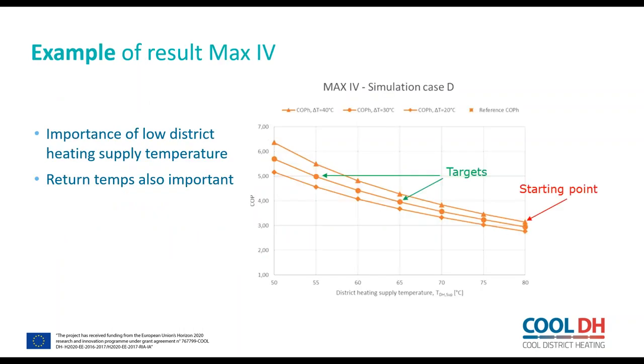An example of the results from the Max 4 looks like this, where we vary the temperature on the hot side, and we also vary the temperature on the cold side. So what you can see in the graph is that at the starting point where we have 80 degrees supply temperature and we have a temperature difference of 40 degrees, you get a COP of about 3. Then with a reduced supply temperature going left in the graph, you increase the coefficient of performance to, at 65, you get a COP of 4. And if we would be able in the future to reduce the temperature even more, let's say 55 degrees, you get a COP of 5.